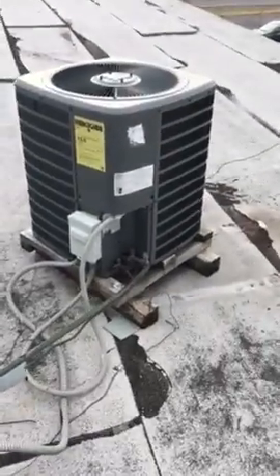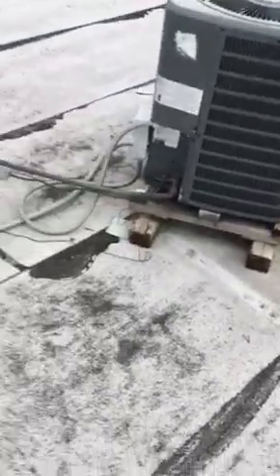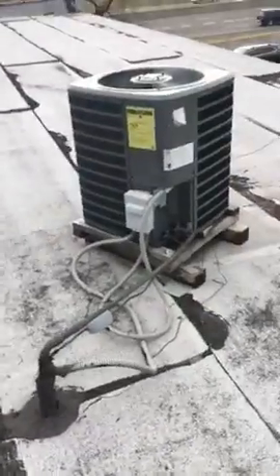I'm up on the roof here at Gregg Harmer's. We're looking at replacing this two-and-a-half ton 13 SEER air conditioner with a 16 SEER heat pump. We're going to need to bring a few 4x4s here to set it on. We're going to reuse the existing line set, so we'll cut it off here and rebraze our lines.